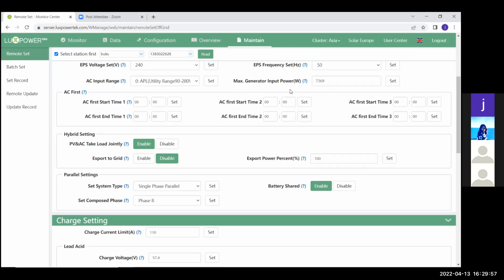If you connect the generator to this machine, you can put the maximum amount that you would like the generator to use of your inverter on this. So if you have a generator that's 5 kilowatts, you don't want it to pull more than 5,000 watts. But in my opinion, if you have a small generator, at least put this value at 50% of the maximum capacity of your generator. So if you have a generator at 5 kilowatts, put it at 2.5 kilowatts, that's 2,500 watts, so that you know that you're safe and you won't overpower your generator and cause dips.